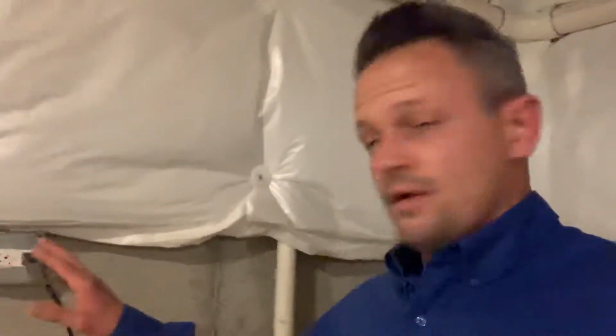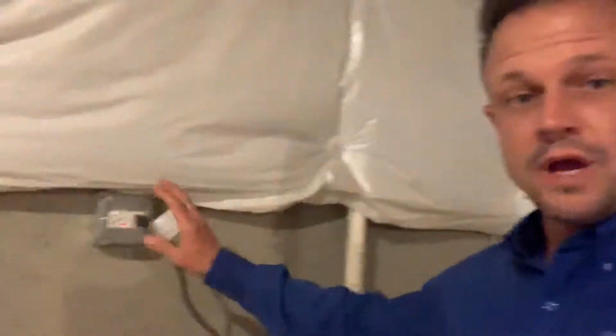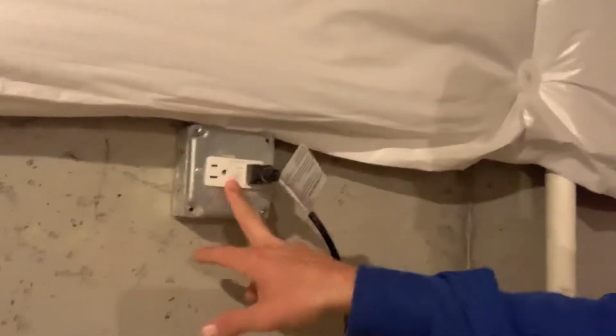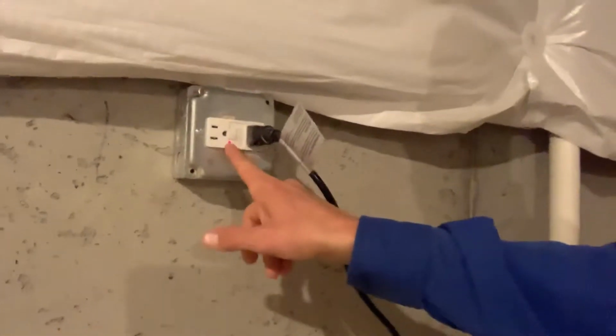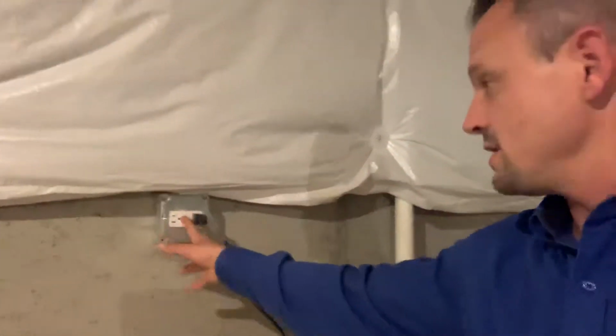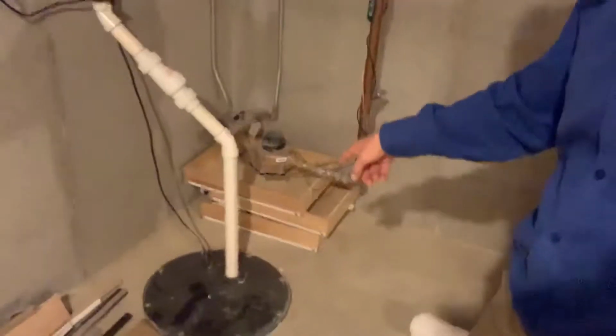Next, we're going to go over to the sump pump. Many municipalities, unless you get an addendum before you're building the house, will require a GFI outlet in every wet location, meaning the basement, kitchens, bathrooms, the garage, and outside. This is a perfect example. Here's a GFI, and when this particular GFI is tripped, it has this red light. Right now, this outlet that powers the sump pump is off. So I'm going to go ahead and reset this. I don't know if you can hear that, but the sump pump just kicked on.